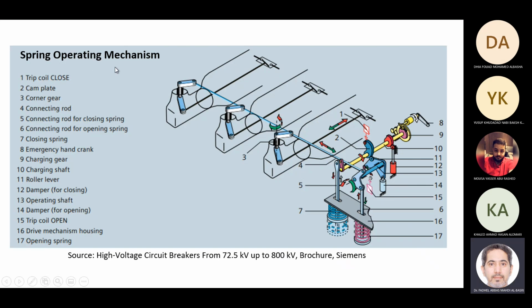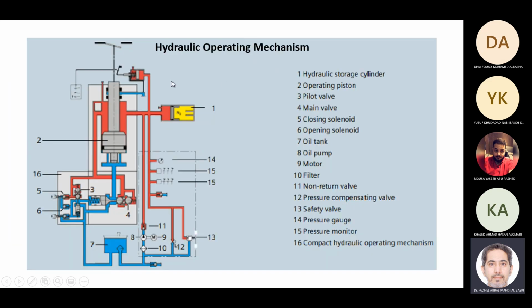This operating mechanism could be a spring, as I showed you, right? So these are the circuit breaker contacts, and it is open or closed based on these two springs. Okay, one is for closing, one for opening. We have different mechanisms, oil or hydraulic based. We use pistons to close and open a breaker, using pressurized oil.